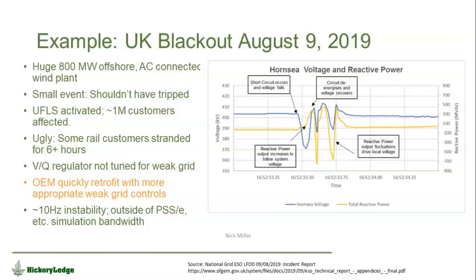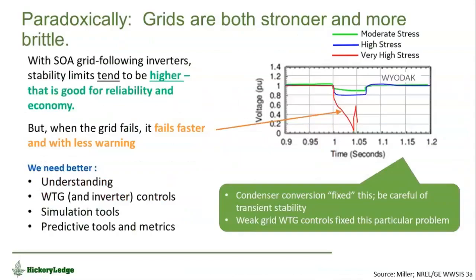I don't need to spend a lot of time on it other than to tell you, first of all, once the event occurred, they went and looked and they said, oh, we can fix the regulators on the grid following inverters. They did that immediately. It took them a day, and the risk went away for this particular problem. B, the phenomenon is about 10 hertz, which means that the simulation, for my earlier point, might not have been terribly meaningful. In any case, they didn't capture this with simulation a priori, which is kind of a mistake.